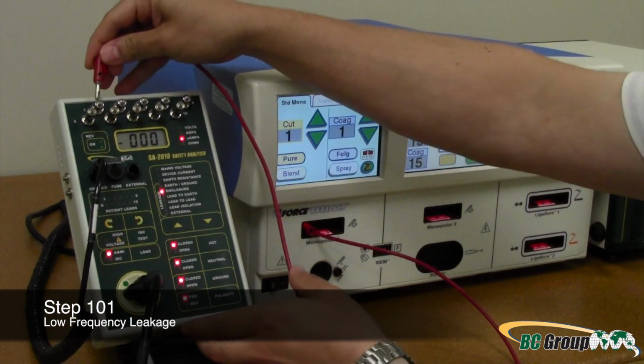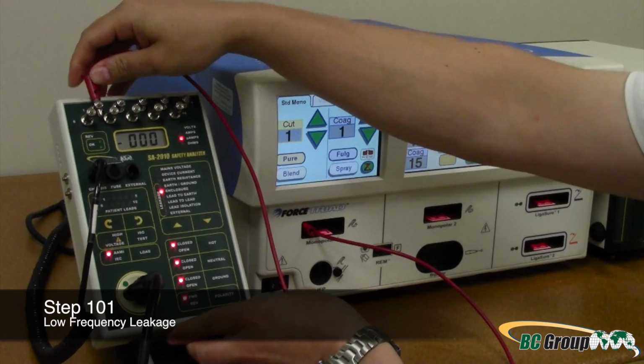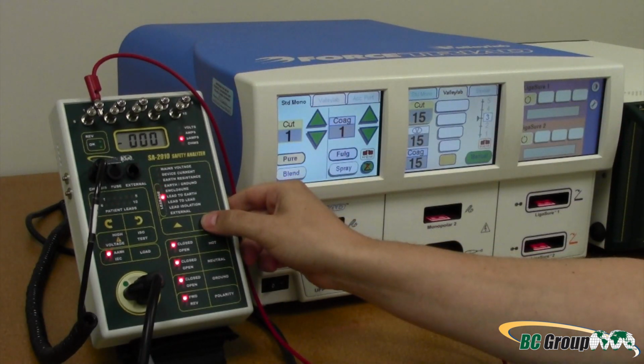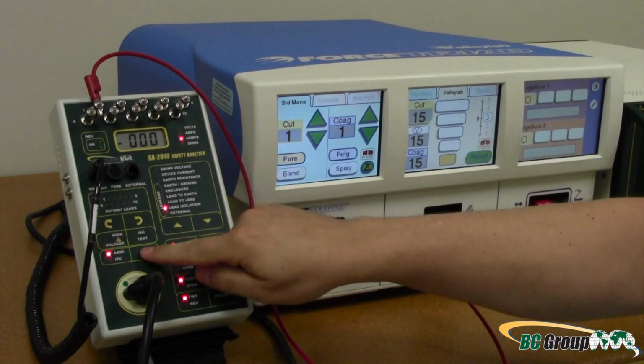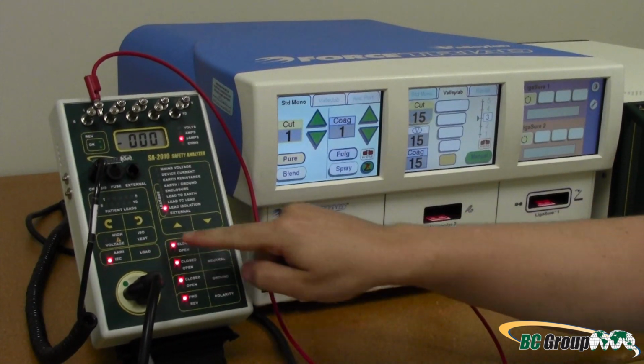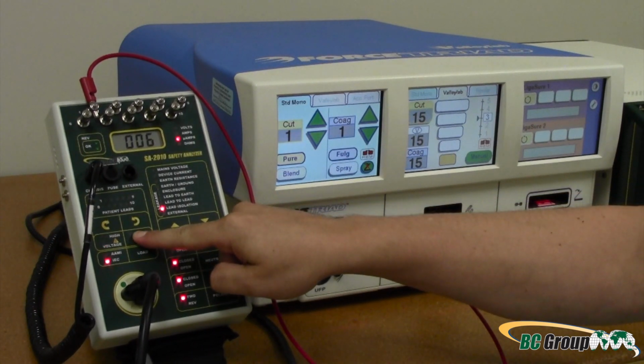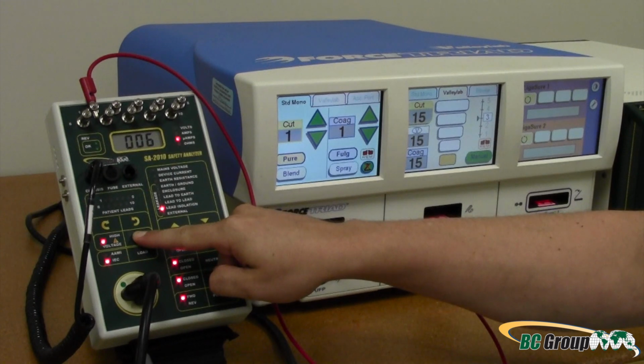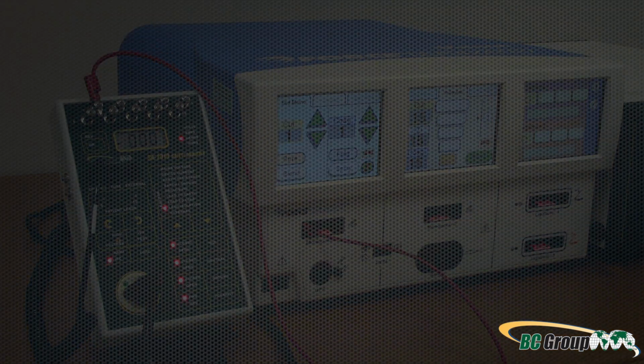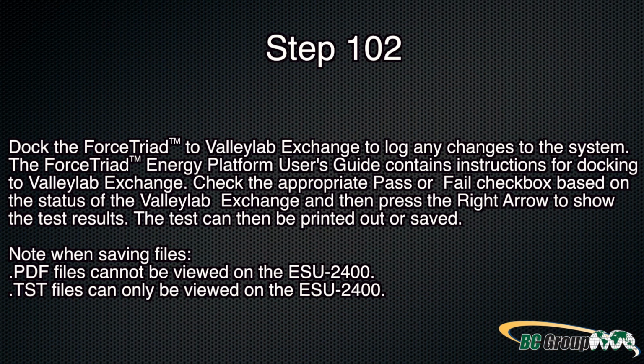Step 101. Low-frequency leakage. Using an electrical safety analyzer, perform a full electrical safety test. Follow the instructions on the ESU-2400 screen to perform the required leakage and ground resistance tests. Step 102. Valley Lab Exchange. Dock the ForceTriad to Valley Lab Exchange to log any changes to the system. The ForceTriad Energy Platform User's Guide contains instructions for docking to Valley Lab Exchange.